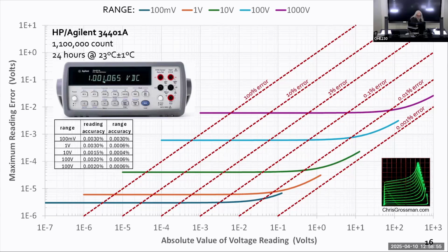As you go lower in voltages, the accuracy of the meter goes down. The flat part is really limited by the range accuracy, or percentage of range. These accuracies are what they guarantee - typically it's better than this, but this is all that's guaranteed. When they send it to the Cal Lab, they measure the meter within this, call it good, and send it back to you.